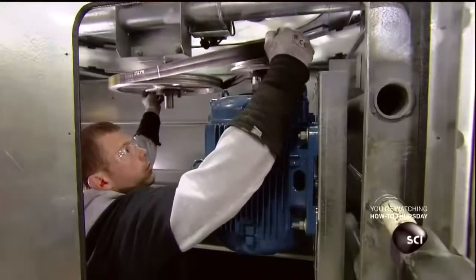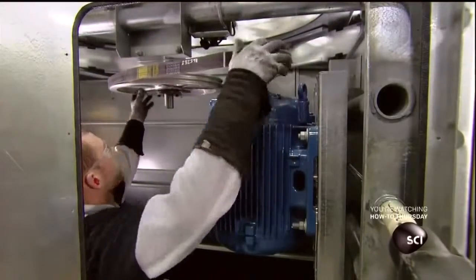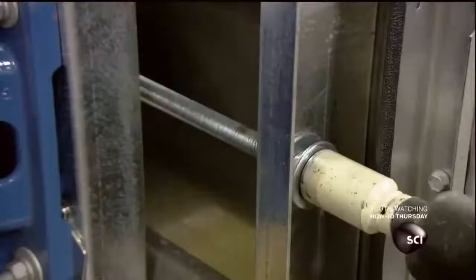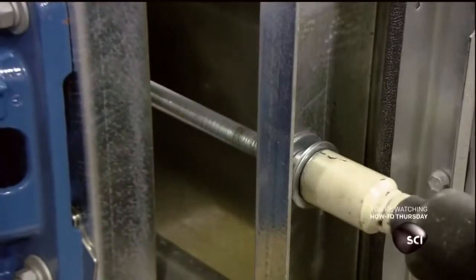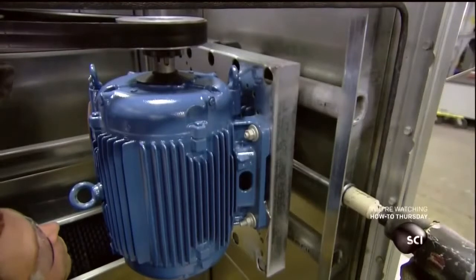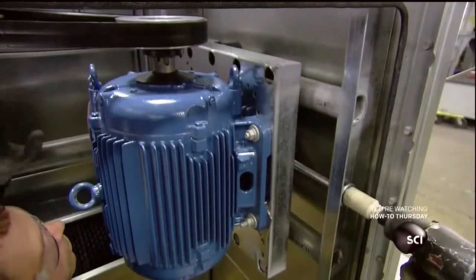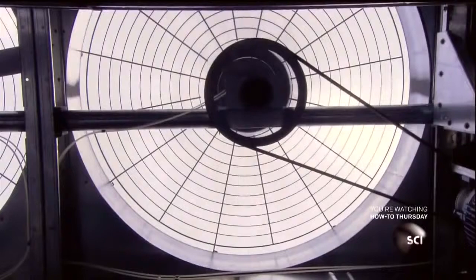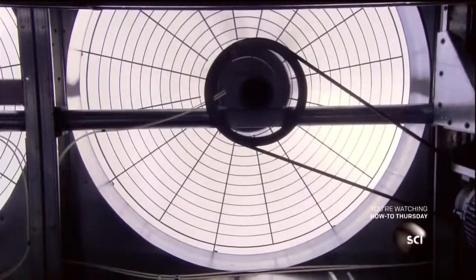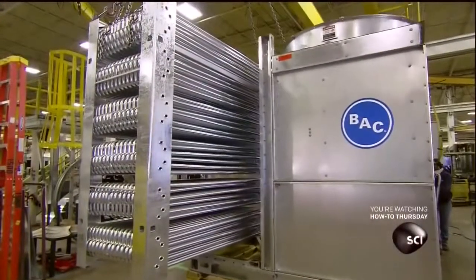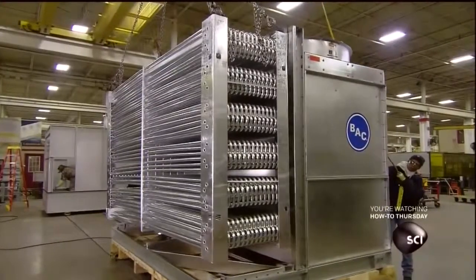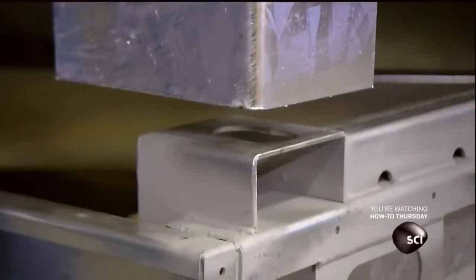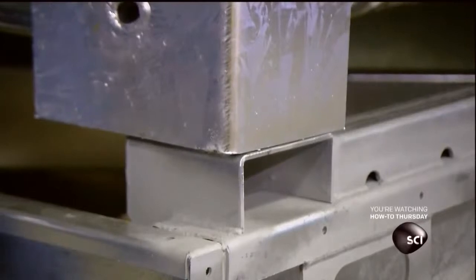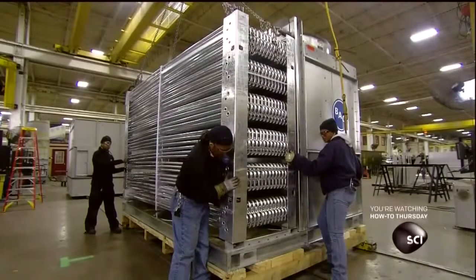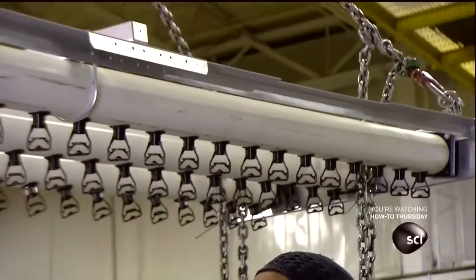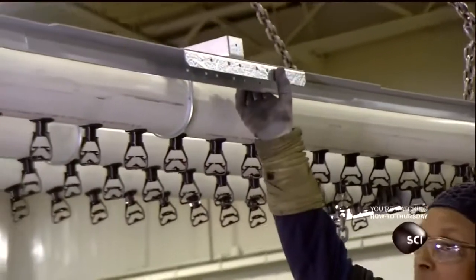Inside the mechanical section, they install the belt that links the motor's pulley to each fan pulley. After tightening the belt screw with an impact wrench, they test the fans. Meanwhile, the coil has been dipped in molten zinc to make it corrosion resistant. Workers mount it next to the cooling tower's mechanical section. They cover it with a steel housing and install the water spray system on top of it.